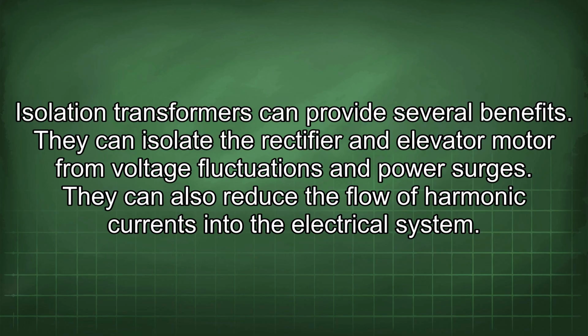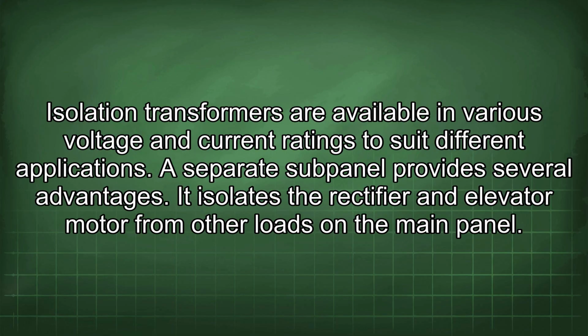Isolation transformers can provide several benefits. They can isolate the rectifier and elevator motor from voltage fluctuations and power surges. They can also reduce the flow of harmonic currents into the electrical system. Isolation transformers are available in various voltage and current ratings to suit different applications.